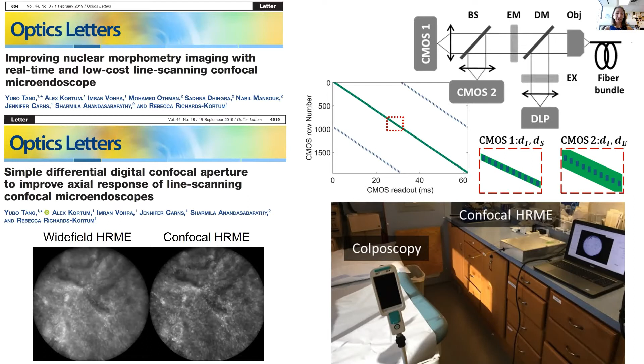Well, the original HRME that I was showing you, typically we would operate that device with the CCD cameras, somewhere between 12 and 15 frames per second. That was good enough to not have motion artifact and to get good quality images. But if you wanted to move the HRME across the surface of the tissue and build up a mosaic as you imaged across the surface, it really wasn't possible, because as you moved it, you would deform the tissue a little bit, and that would make the images blurry. And it wasn't possible for the providers to hold the probe steady enough without a probe holder.